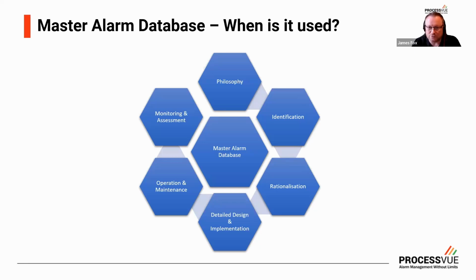So when we're carrying out audits, etc., we can make sure that no alarms are missed. Used during rationalization, it provides the ability to perform centralized rationalization, and it helps store the supporting information that comes along with rationalization, optimization, and documentation, such as the cause of the alarm, the consequence of missing. DCSs, SCADA, PLC systems are not really geared up for storing this supporting information, and that makes the master alarm database the perfect place for storing that information.